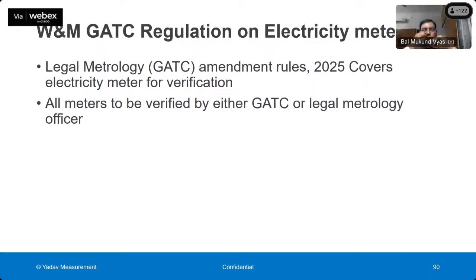All of you must have noticed that the Legal Metrology Department has issued a GATC regulation on electricity meters also. In fact, this is applicable to about 18 instruments, for example gas meters, electricity meters, BP instruments, and so on. This Legal Metrology GATC Amendment Rule 2025 also covers electricity meters, and because this is a gazette issued by the Government of India, it requires that all meters should be verified before they are installed and at the periodicity which is specified.